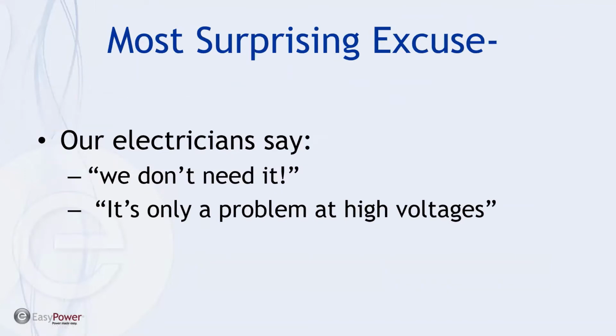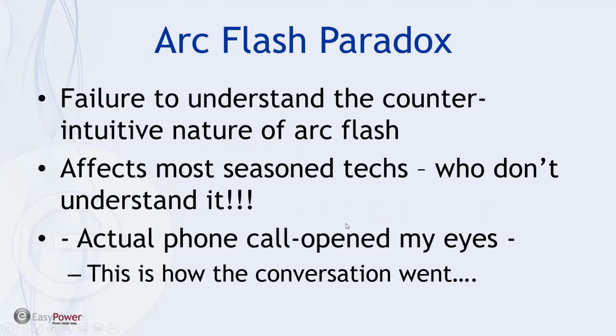But the most surprising excuse was that our electricians say we don't need it, it's only a problem at high voltages. Well, that brought me to understand the arc flash paradox, and it's a failure for seasoned personnel to understand the counterintuitive nature of arc flash, and it affects the most seasoned techs who don't understand it. And I put myself in this category when I first joined EasyPower.